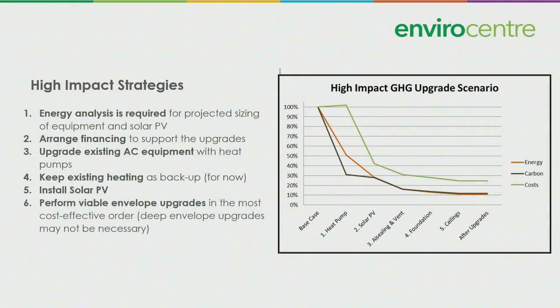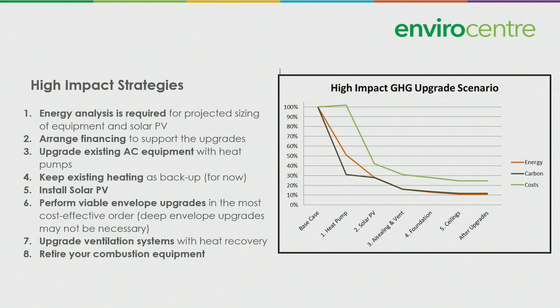Then perform your viable envelope upgrades in the most cost-effective order. Deep envelope upgrades may not be necessary to hit the target. If you look at the chart on the right, we reached 90% reduction of carbon and energy use. And upgrade your ventilation systems with heat recovery. What happens when you're tightening up these buildings is they become more airtight, so it becomes more crucial to provide effective ventilation. Finally, when you've done all the other upgrades and your combustion equipment is reaching the end of its life, retire your combustion equipment and replace it with something that produces heat through electricity.